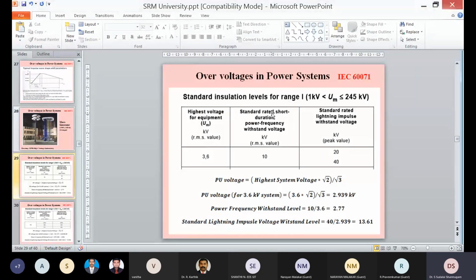So the first thing I should know is, when the highest system voltage is 3.6 kV, what is the per unit value? That I should be aware of. Please write down this calculation. Per unit voltage is equal to highest system voltage into root 2 divided by root 3. So for a 3.6 kV system, the per unit value is equal to 3.6 kV into root 2 divided by root 3, which is 2.939 kV. This is 1 per unit for a 3.6 kV system.